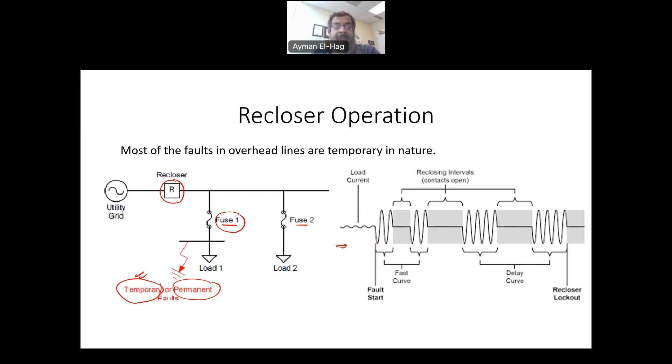So at the beginning of the operation of the Recloser, the Recloser is the primary protection system, the fuse is the backup protection system. So it does that usually two times: open, close, open, close very, very fast. So if the fault cleared by itself, then the fuse is not melted and the system will restart the operation without any problem.